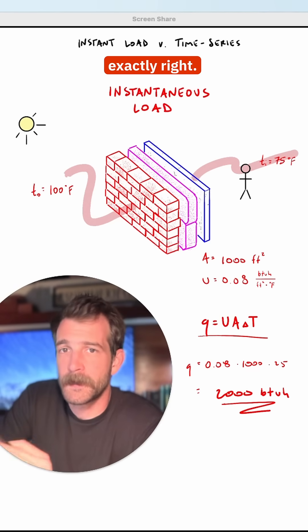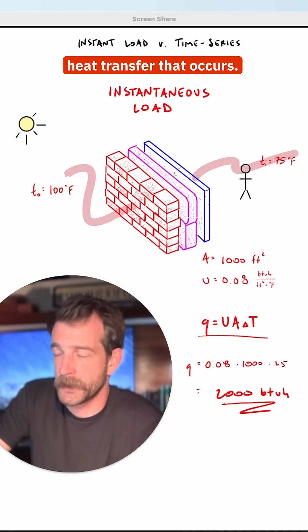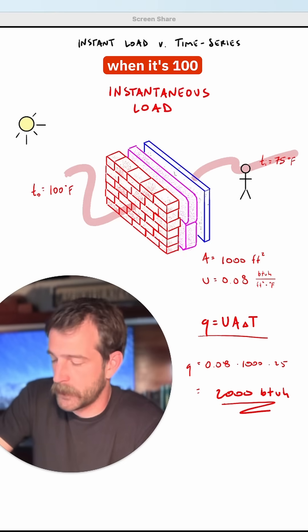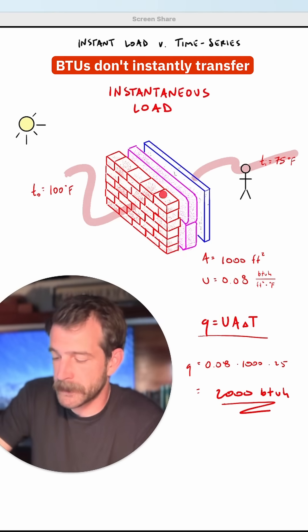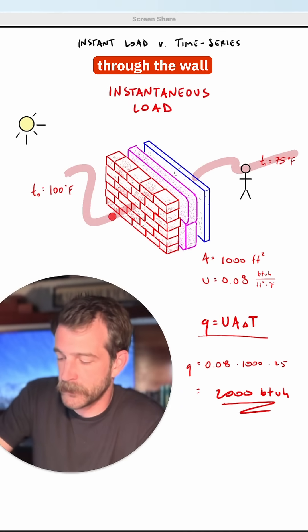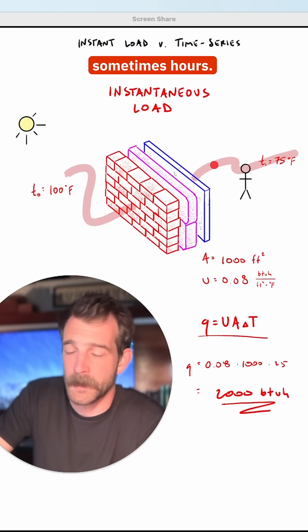It's a good estimate, but it's not exactly right because there's a time delay to the heat transfer that occurs. If we're calculating this for 2 p.m. when it's 100 degrees outside, these 2000 BTUs don't instantly transfer to the space. They may transfer through the wall assembly over time, sometimes hours.